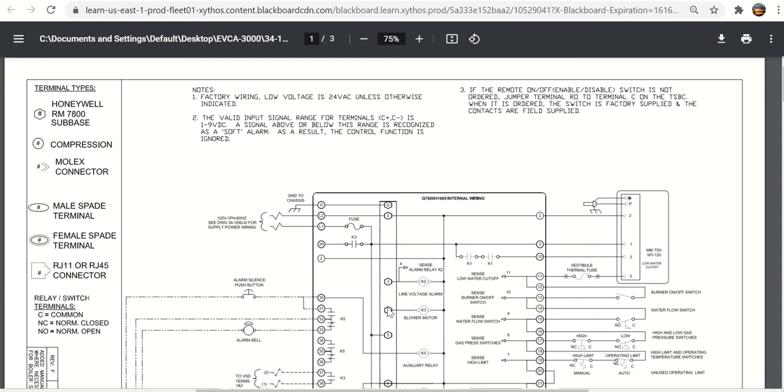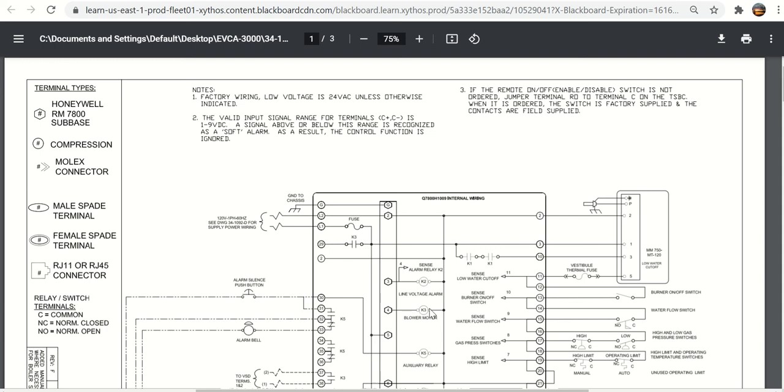Here is terminal number three, terminal number four. Terminal number three is the alarm relay. Anytime you have power on terminal number three is if the flame safeguard went into alarm. Terminal number four would be anytime that you want the blower to start.